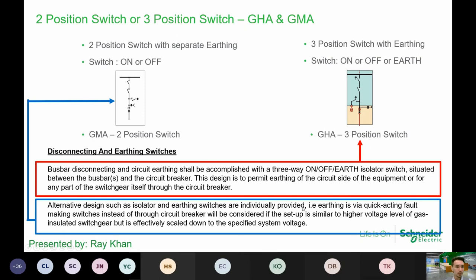For example, where the earthing is via a quick acting making switch instead of through the circuit breaker. So this gives an option for the two position switch as well. The two position switch has been tested also, based on the fault making capacity of 25 kA, 3 seconds.